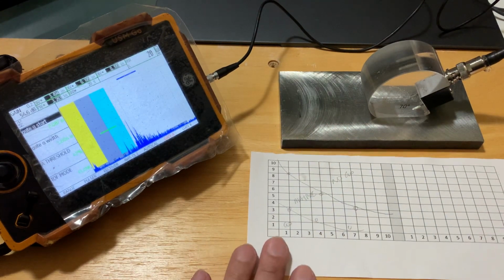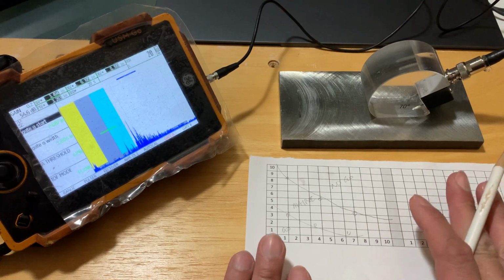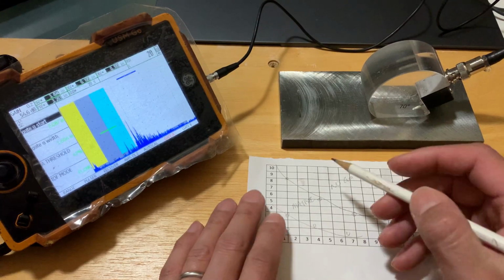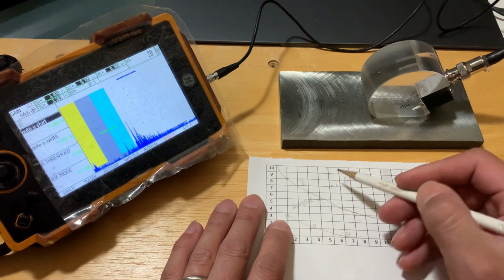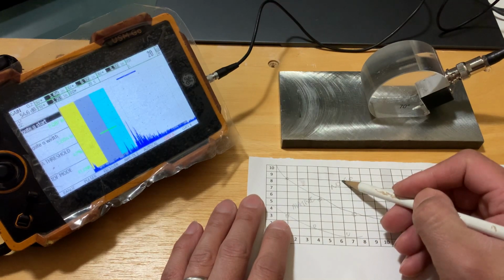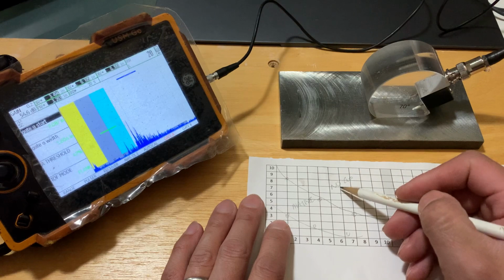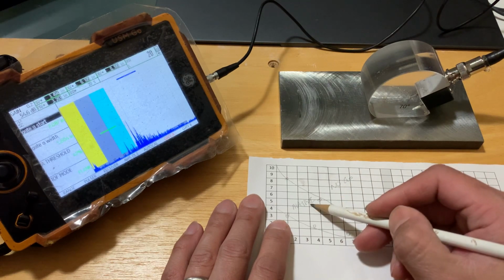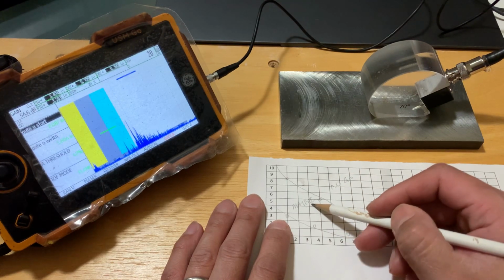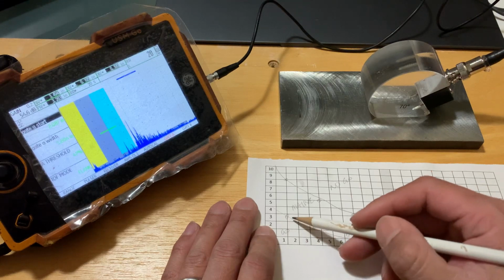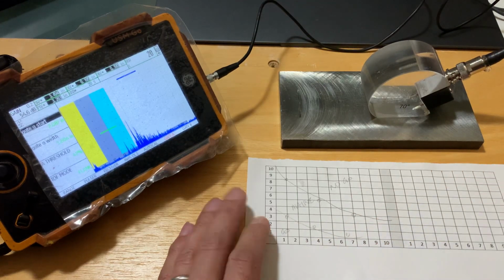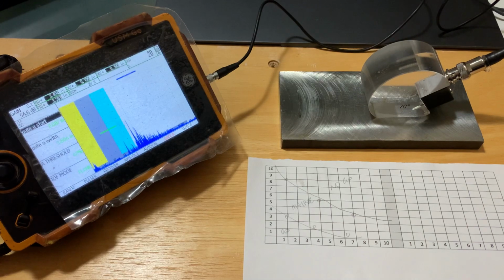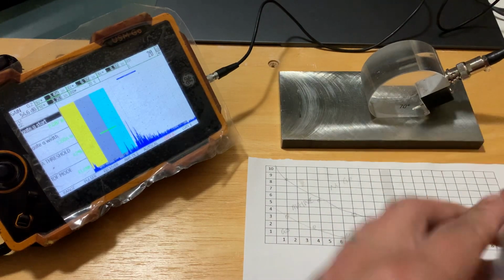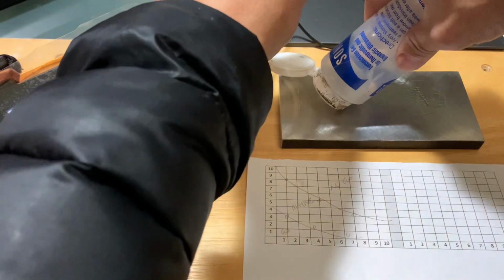And so when you're done calibrating and you're setting up, usually you set up with the material that you're using, so that way you could determine in a quick glance if it's a no-go, as in there's a flaw in there that needs to be cut out, or it's a flaw that needs to be evaluated a little more, or it's a flaw that does not meet the criteria to be investigated further. So it kind of speeds things up a little bit. So I'm gonna throw some couplant on here. And I got my screen.